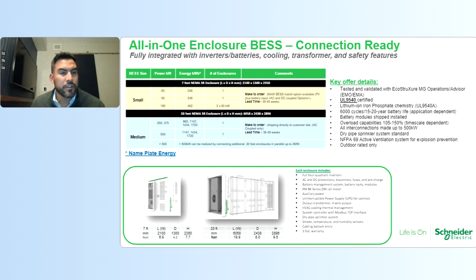Then we jump up to a 250 kW energy storage system up to 500 kW. We have the capabilities, apparently, at least 4 of these, to get you 2 megawatts. But to give you a size of these energy storage systems, the small is a 7-foot container for us. That's an industrial container that's designed to be installed outdoors. And then the next size up is the 250 kW, which is a 20-foot container. Depending on where this energy storage system will be located, AHJs have different requirements on clearances. So we definitely recommend you get in contact with the local jurisdiction to understand the installation requirements.